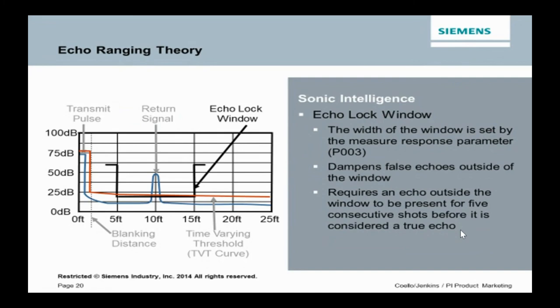One of the things you'll find on the whole Hydroranger, Multiranger, is if you walk up to the display and you have a pretty static process, and all of a sudden you're looking at a level and it's like 8.0, and then it goes 8.2, 7.9, 8.1, 7.8, 8.0, and it's sitting there not real stable in the measurement, even though your tank is stable, that's a pretty good indication that you have that echo lock window opened up way too wide.